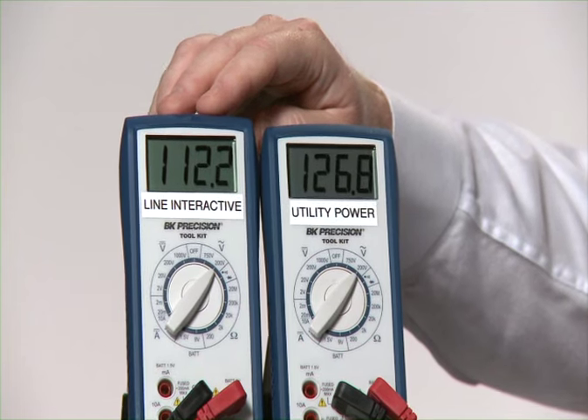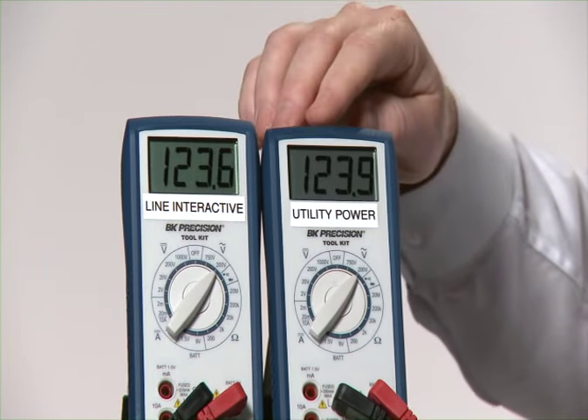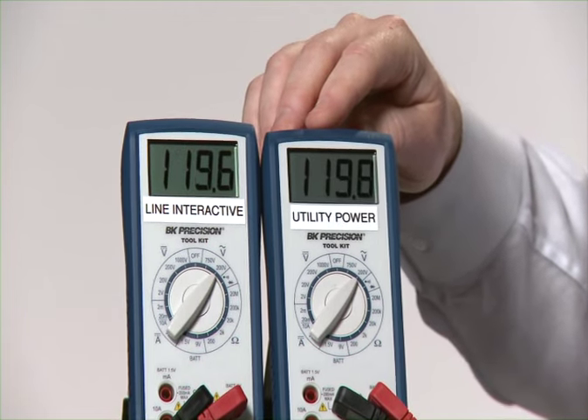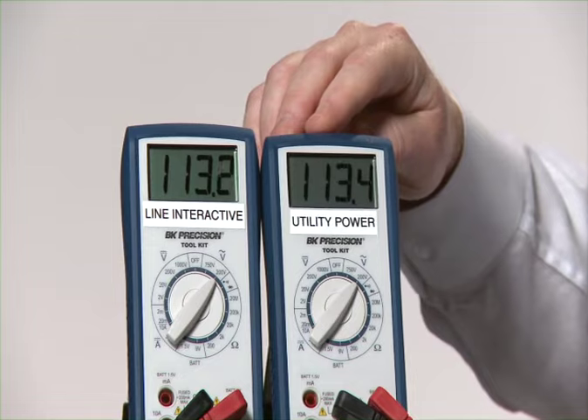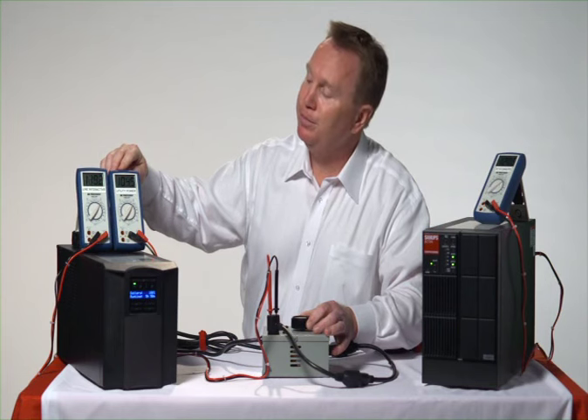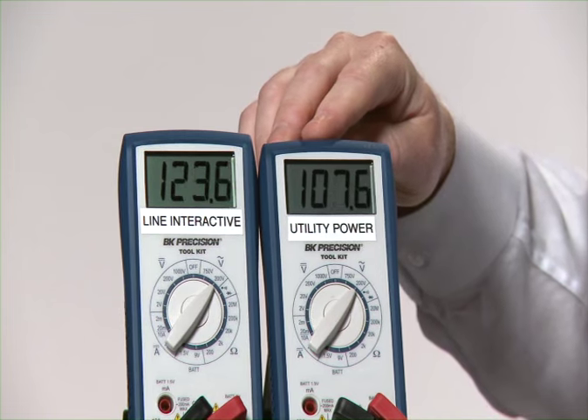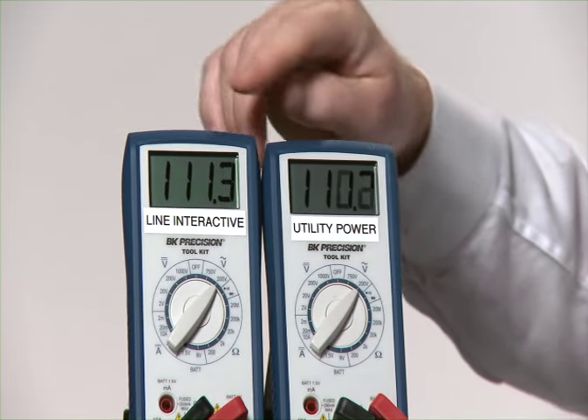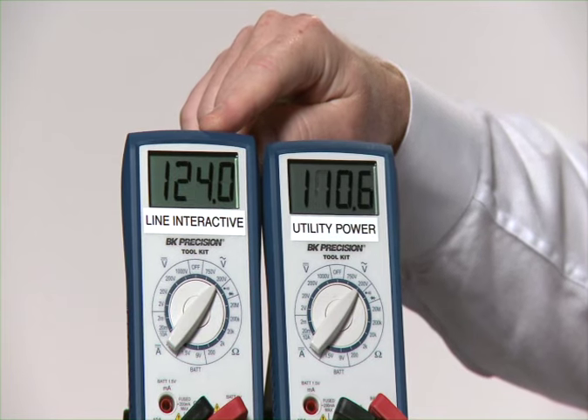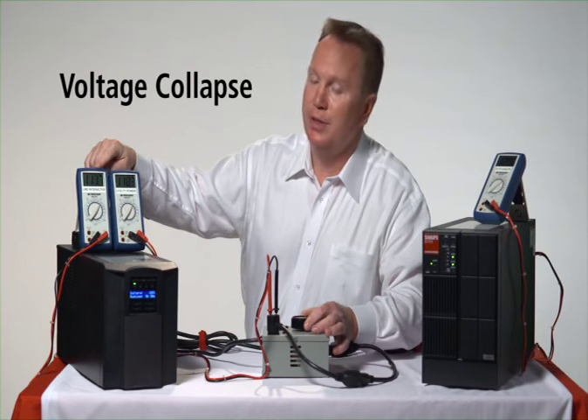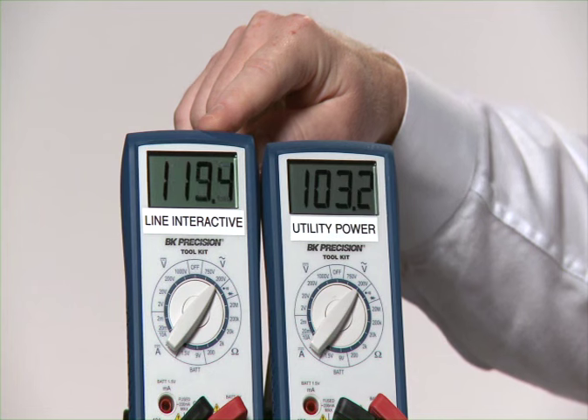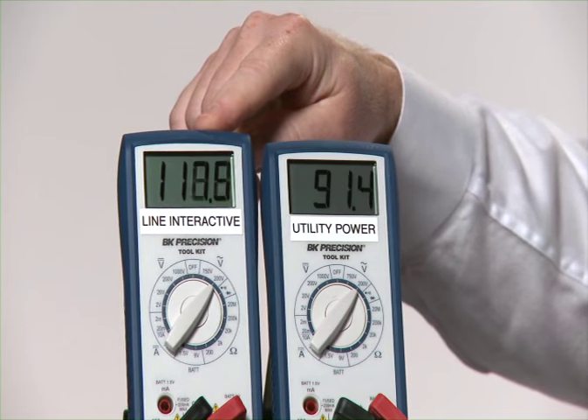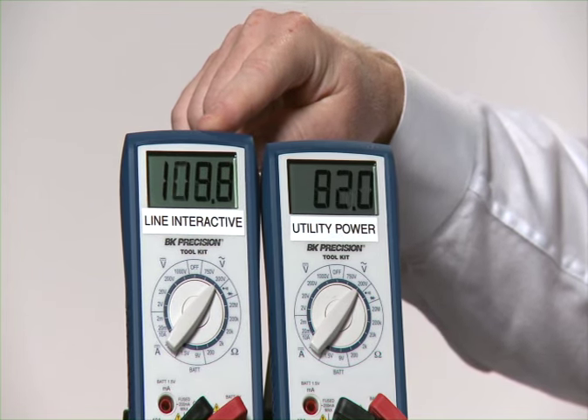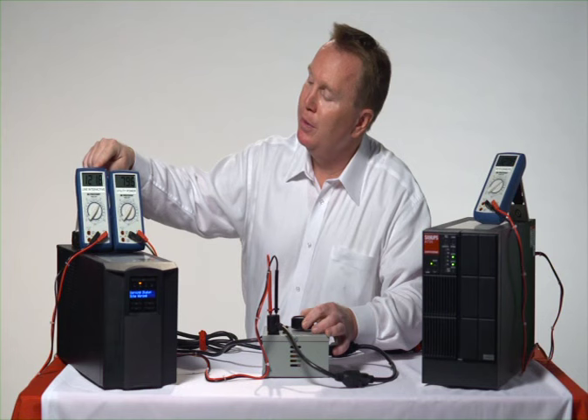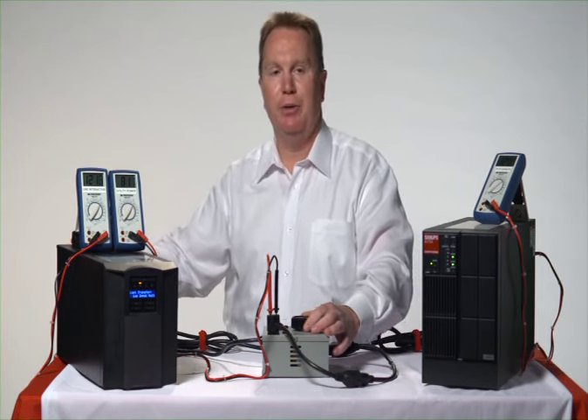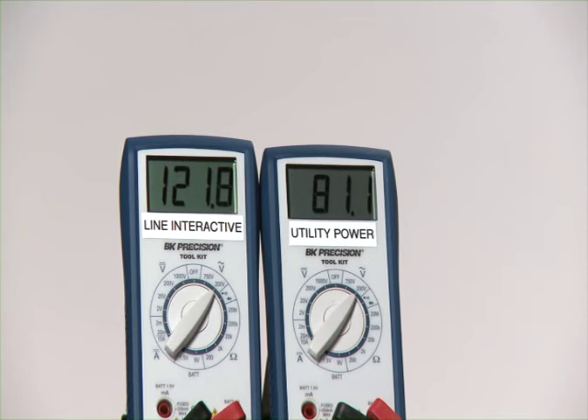Back to normal voltage. Please notice the output of the line interactive unit throughout this, down into our sag. As we sag down, again, you're hearing the click of the AVR. We'll drift a bit. That AVR is doing its best to maintain power quality. Watch the variation in voltage. Now our utility decides to collapse. As we get down to 90s, we'll proceed down to 80s. Sit on 80 volts here. Now we're in a full battery event. Your batteries have kicked in and your power is restored.